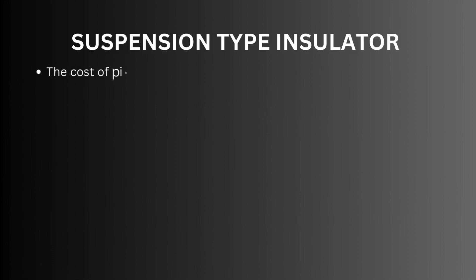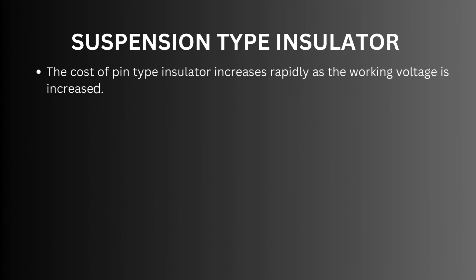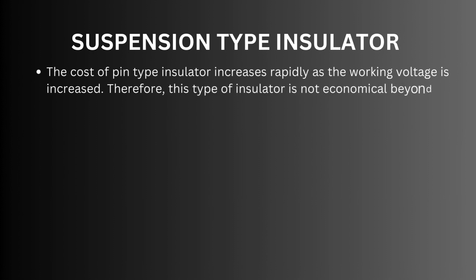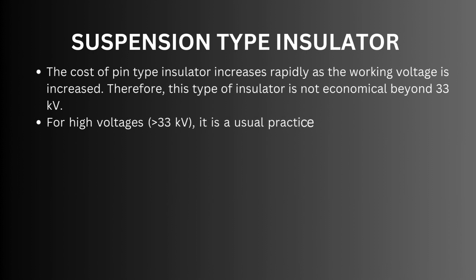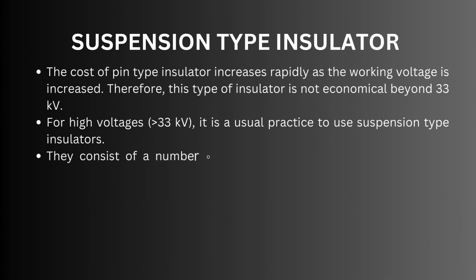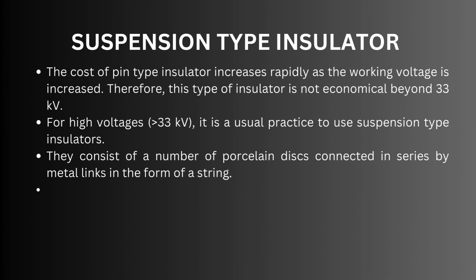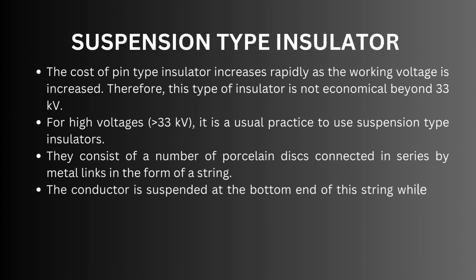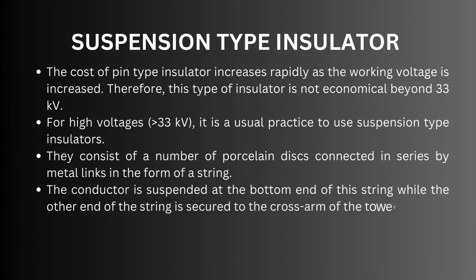Suspension type insulator: the cost of pin type insulator increases rapidly as the working voltage is increased, making it uneconomical beyond 33 kilovolts. For high voltages greater than 33 kilovolts, it is usual practice to use suspension type insulators. They consist of a number of porcelain discs connected in series by metal links in the form of a string. The conductor is suspended at the bottom end of this string while the other end is secured to the cross arm of the tower.